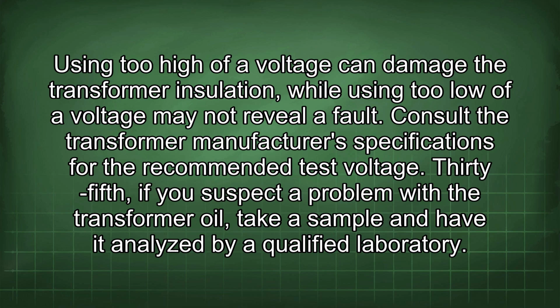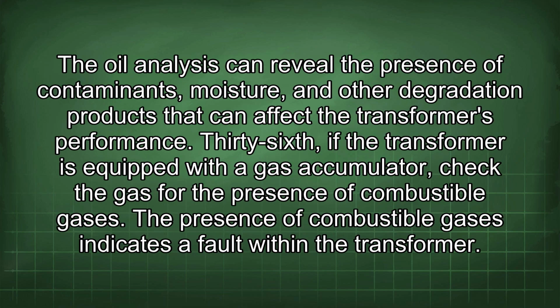35th, if you suspect a problem with the transformer oil, take a sample and have it analyzed by a qualified laboratory. The oil analysis can reveal the presence of contaminants, moisture, and other degradation products that can affect the transformer's performance. 36th, if the transformer is equipped with a gas accumulator, check the gas for the presence of combustible gases. The presence of combustible gases indicates a fault within the transformer.